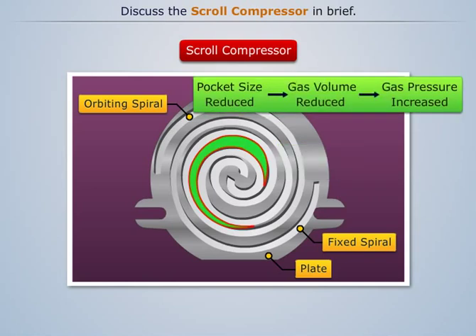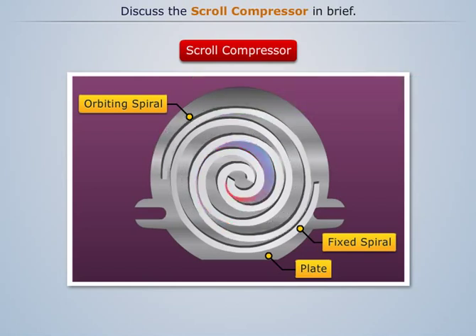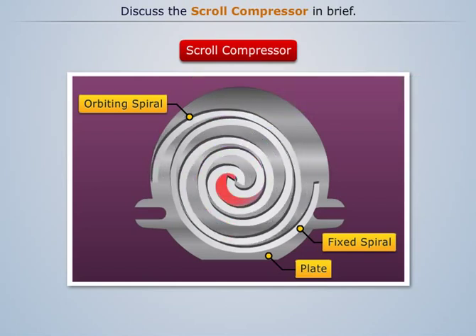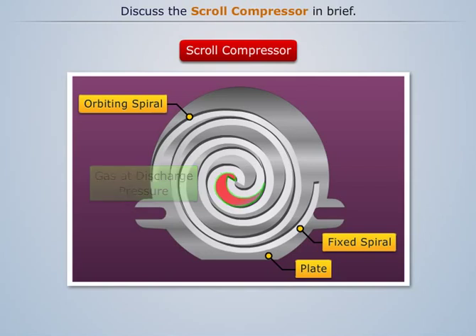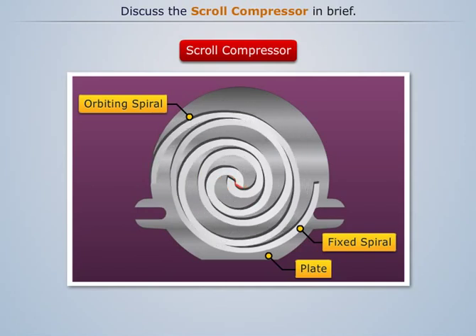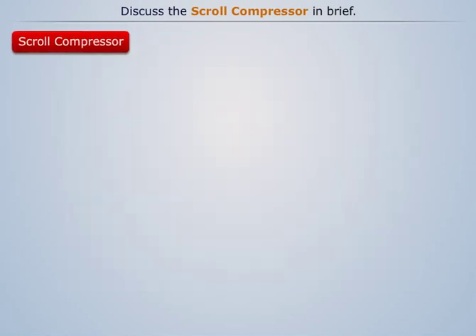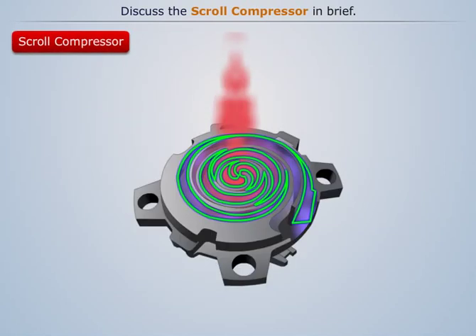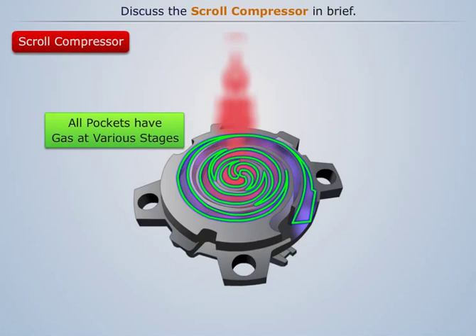This spiral inward movement reduces the volume of the gas present in the pocket, thereby increasing its pressure. Further movement of the orbiting scroll causes the gas to reach the center of the compressor, increasing its pressure to discharge pressure. The gas then gets discharged from the center of the compressor. This concludes the working of the scroll compressor. All pockets between the scrolls have gas in various stages of compression.